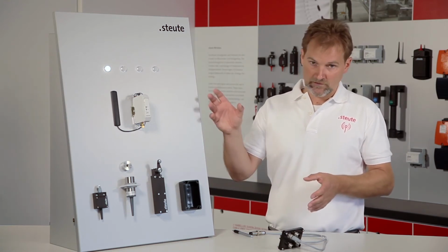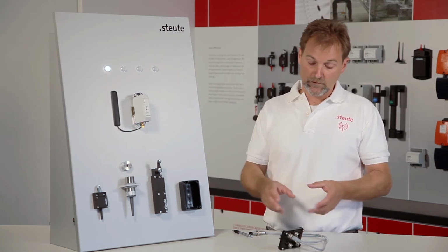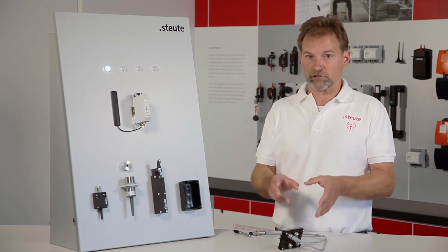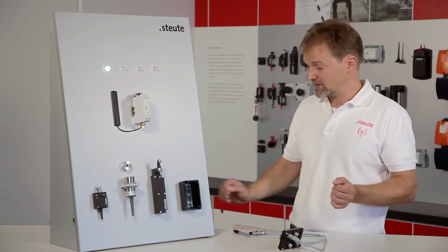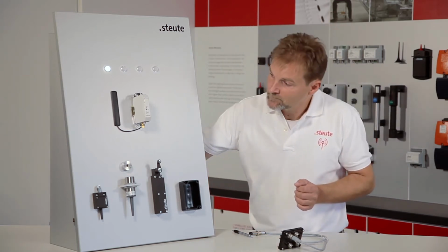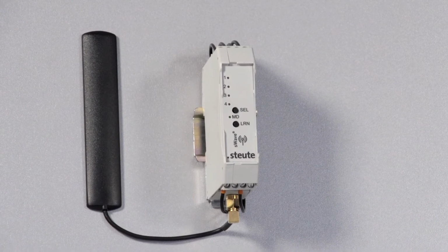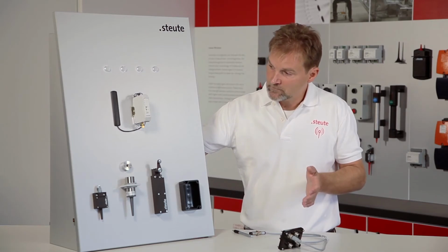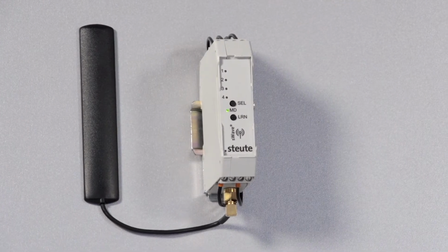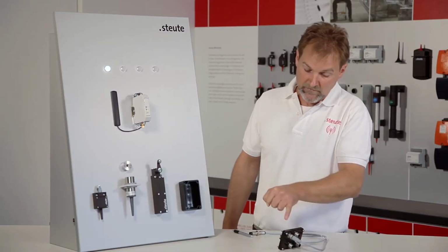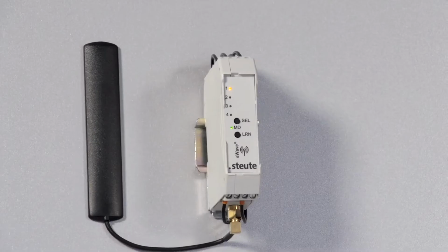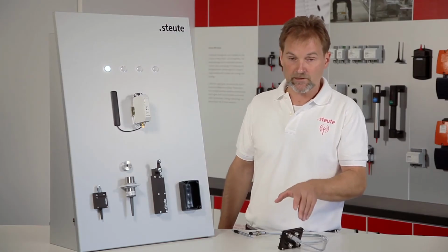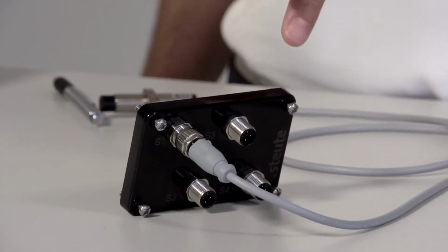But because we have a status signal every 10 seconds, if the receiver is then switched off and back on again, the status signal would still be transmitted at the latest after 10 seconds. I should like to demonstrate this briefly by disconnecting the receiver from the power to simulate our example of a power cut in the production hall. Then the power goes back on, as I shall also simulate, and we can see that after just a few seconds the status signal is communicated. This means that the relay does not have to remain disengaged because the function status signal communicates the switching status to the receiver after 10 seconds.